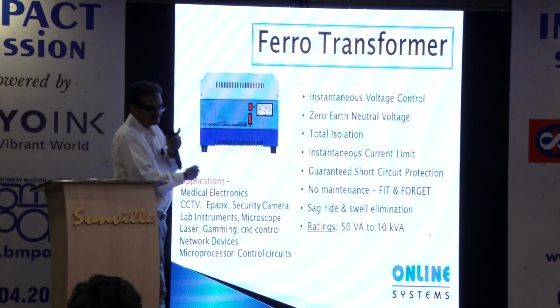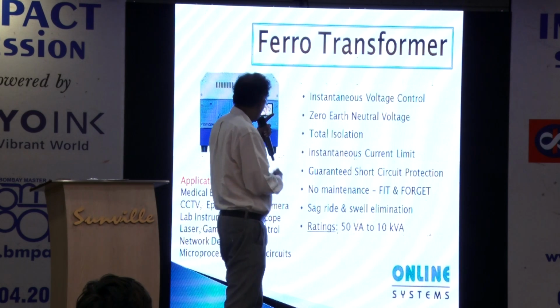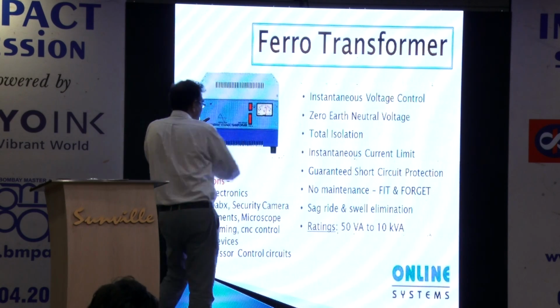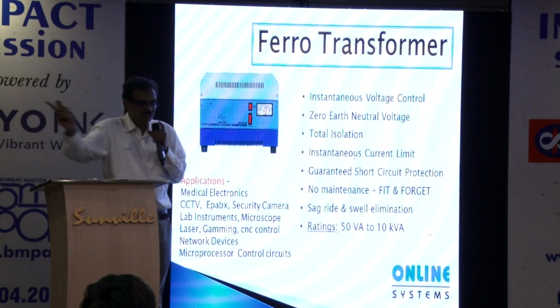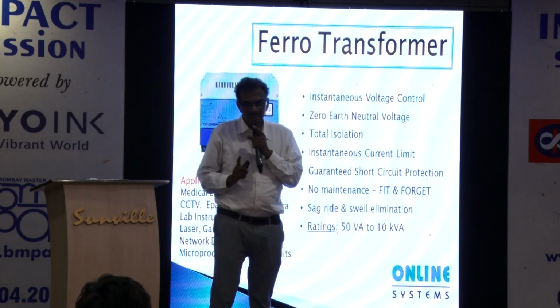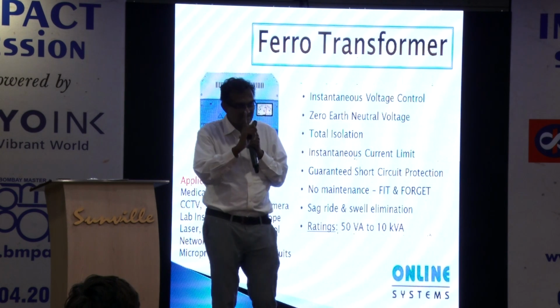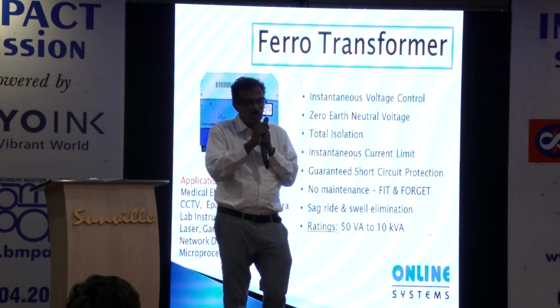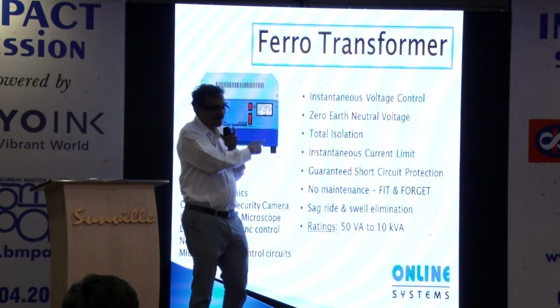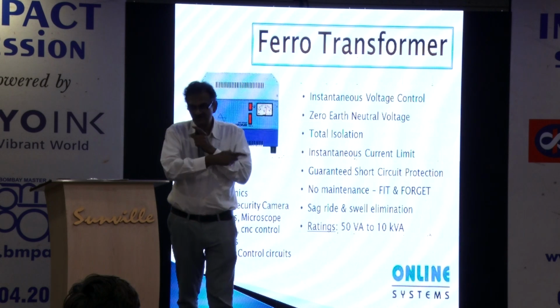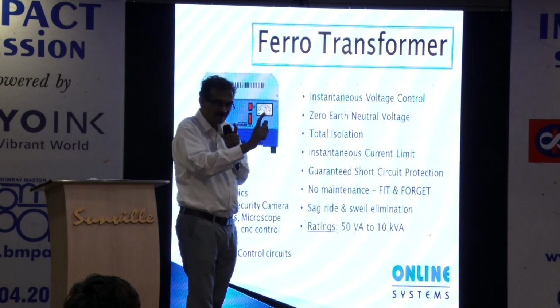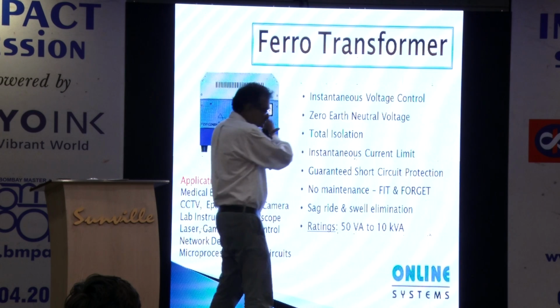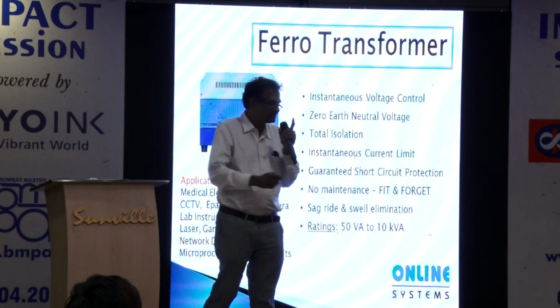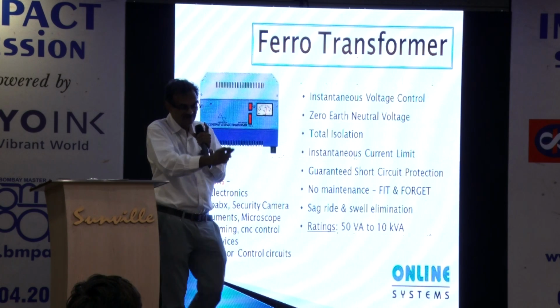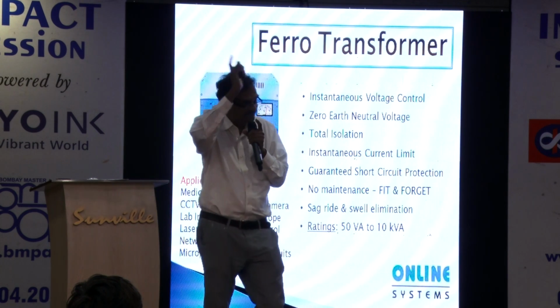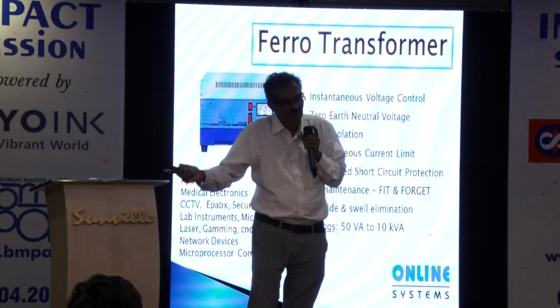Now this is a device we've been selling for 30 years, a ferro transformer. Any voltage change will be corrected within one cycle of the waveform, that is 20 milliseconds, and the output will remain rock steady. You give it a sudden high voltage, nothing will happen, it's a saturated core transformer, output will still be rock steady. It has total isolation, and in a demonstration on the secondary side, I will short phase and neutral, nothing will happen. The magnetic flux will collapse and be normal again.